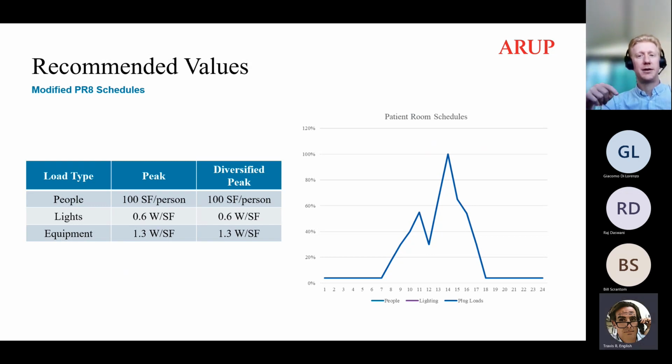load should look like across a diversified set of zones. Let me say that back to you and see if I understood it right. What I think you're telling me is that basically these values are kind of for the energy modeling and maybe appropriate for the overall tonnage and system sizing. However, you would not use this to size the individual patient room cooling capacity, right? Because you'd wind up low significantly.